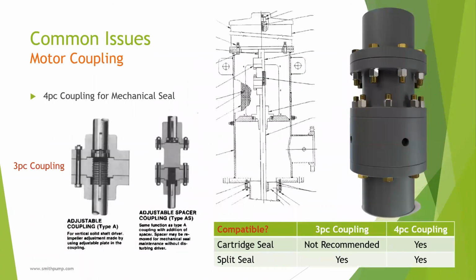The motor coupling is also related to the seal type used. If using a mechanical seal, we recommend using a 4-piece coupling. While a 3-piece coupling can be used, the motor would have to be removed if replacing a cartridge seal. So a 4-piece coupling does not require the motor removal because it has a spacer section shown right here. Removing the spacer creates a large enough gap for the cartridge seal to slip out. It's a huge time saver for seal changes.